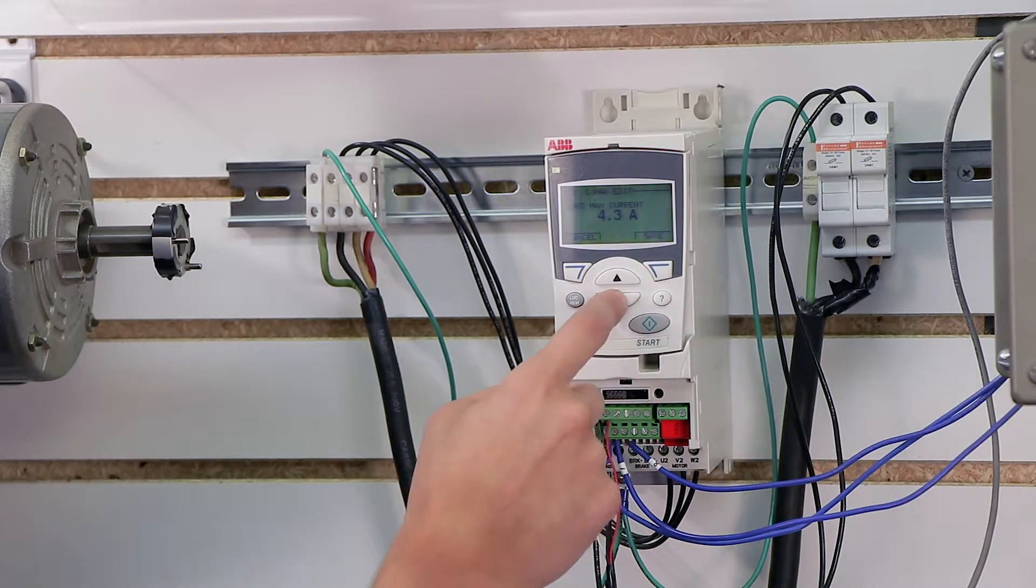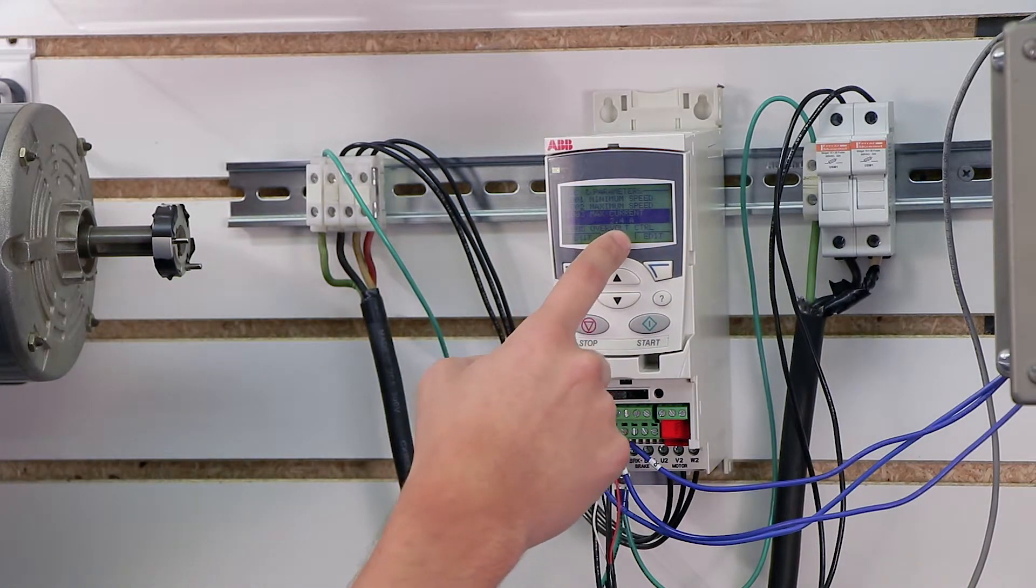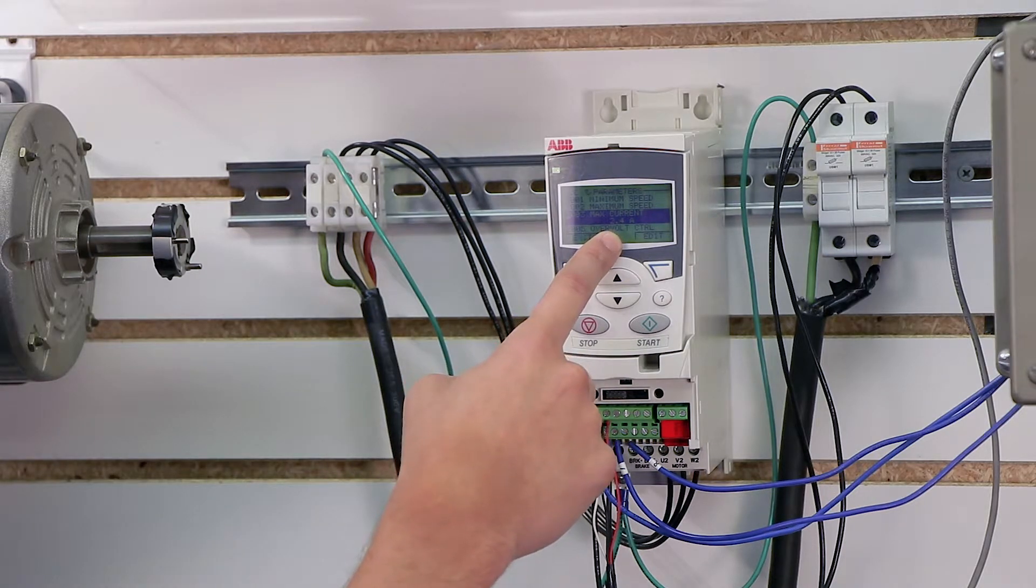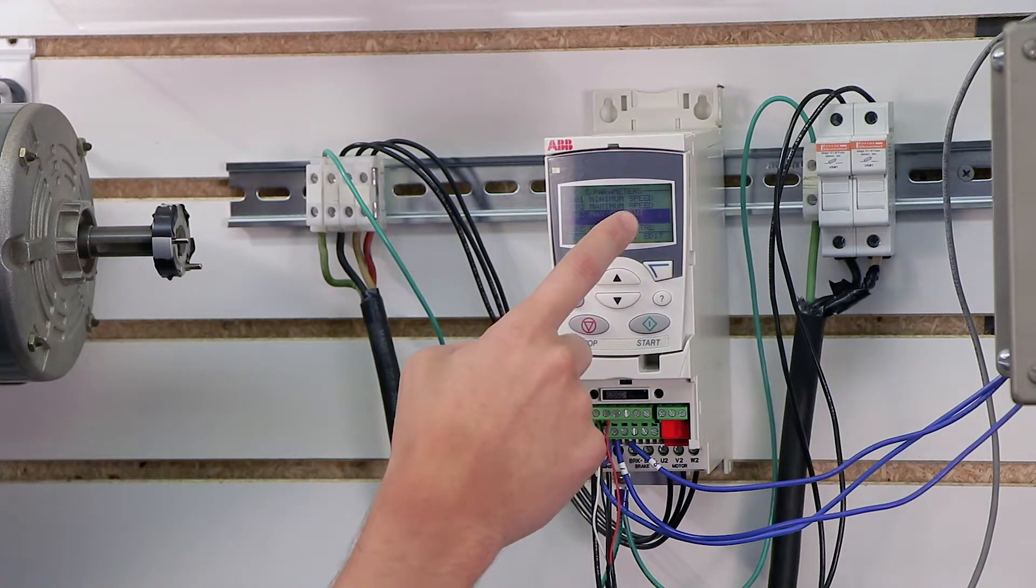This is actually a step that a lot of people tend to ignore, which they shouldn't, because this can actually let the drive put more current into your motor than it's designed to handle. So you want to make sure you set this parameter to 2.4 amps or whatever the full load amp rating is on your motor. And that sets the overload.